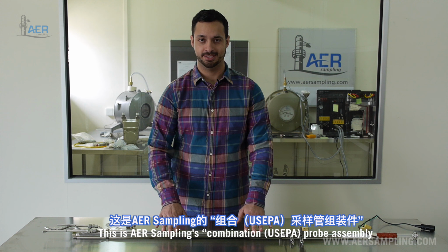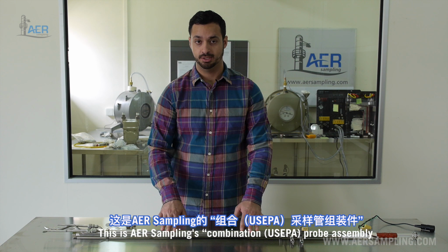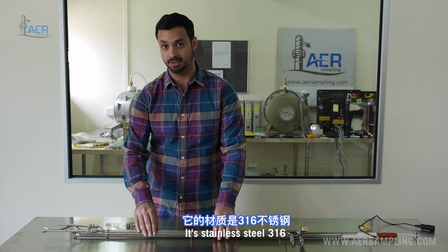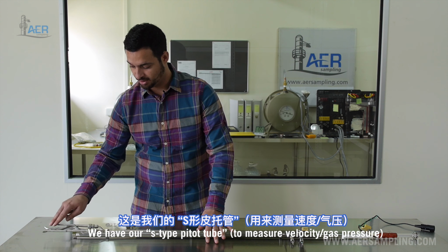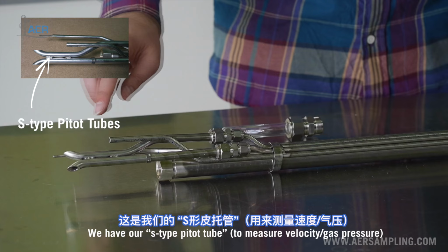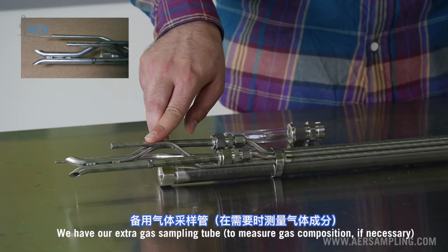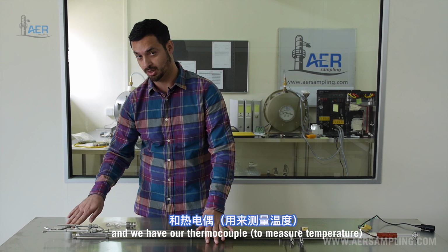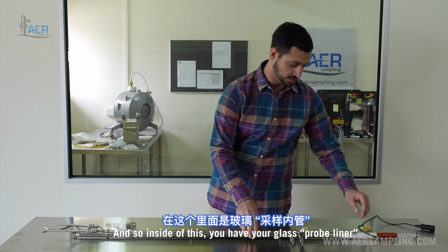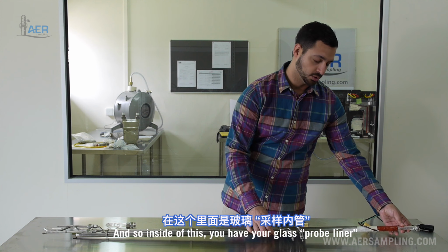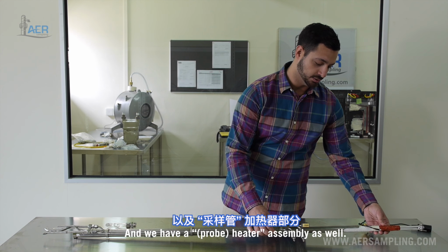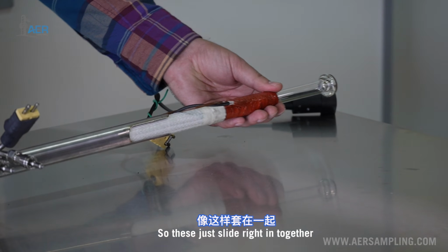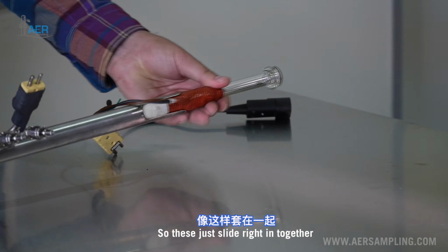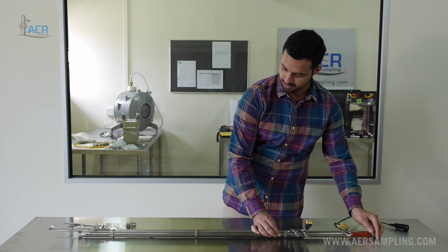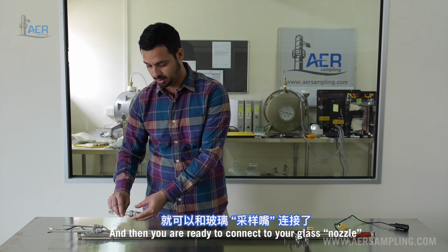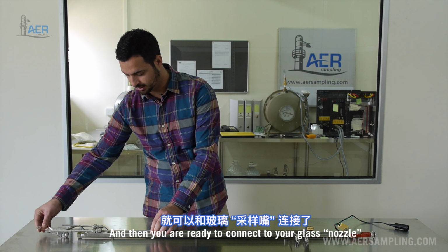This is Aer Sampling's combination probe assembly. So it's stainless steel 316. We have our S-type pitot tubes, we have our extra gas sampling tube, and we have our thermocouple. And so inside of this, you have your glass probe liner, and we have a heater assembly as well. And so these just slide right in together. And then you're ready to connect to your glass nozzle on this end here.